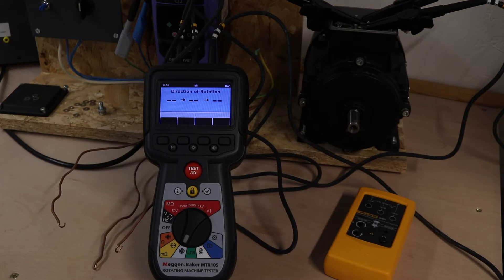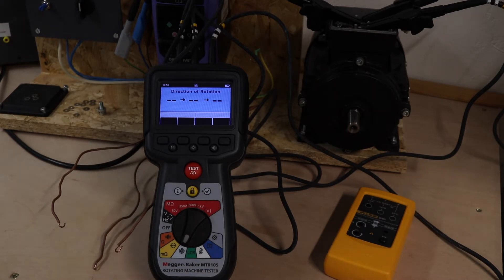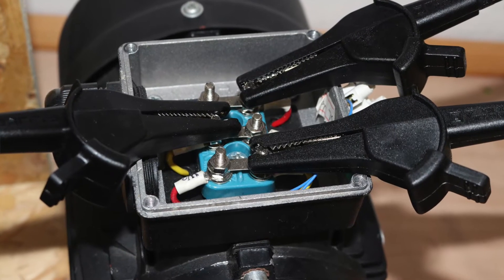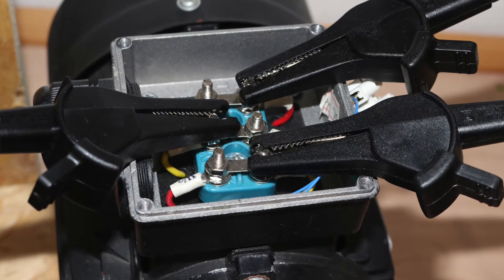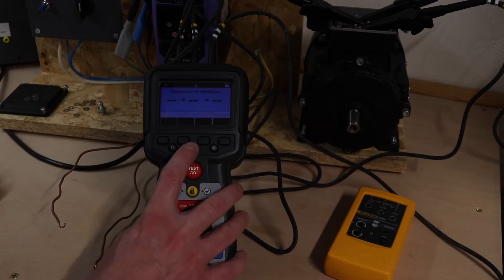I have the MTR105 set up to do a directional rotation on the motor. The leads are already connected up. I'm using the leads from the Fluke 9062 for both tests. I'll put a picture up of the connections onto the motor but we're set up here.